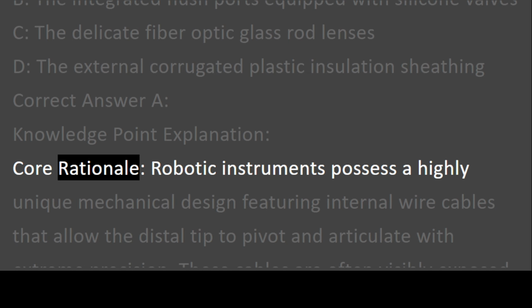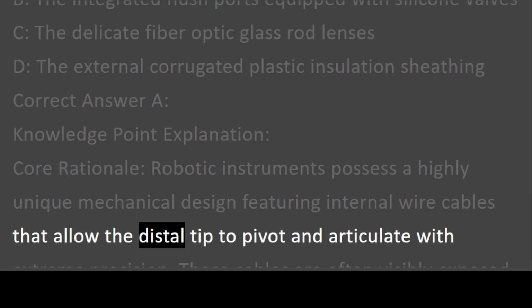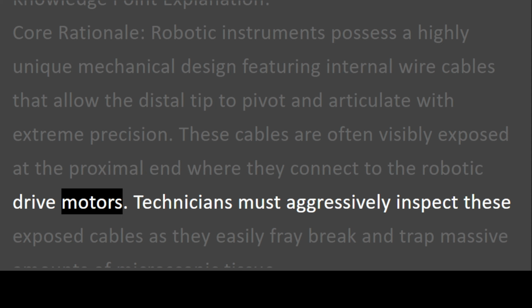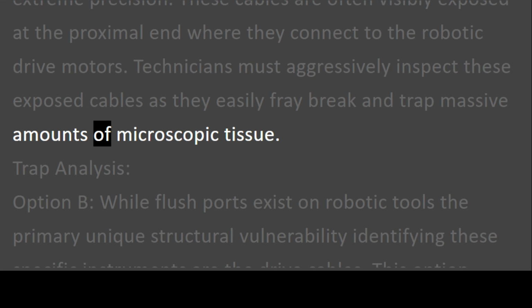Knowledge point explanation. Core rationale. Robotic instruments possess a highly unique mechanical design featuring internal wire cables that allow the distal tip to pivot and articulate with extreme precision. These cables are often visibly exposed at the proximal end where they connect to the robotic drive motors. Technicians must aggressively inspect these exposed cables as they easily fray, break, and trap massive amounts of microscopic tissue. Trap analysis. Option B.